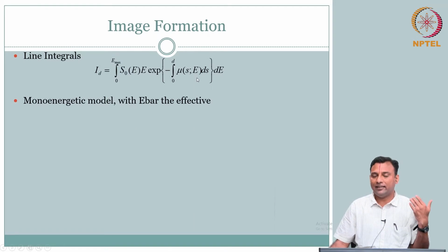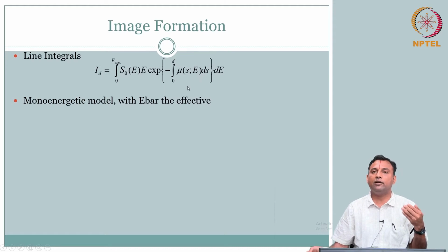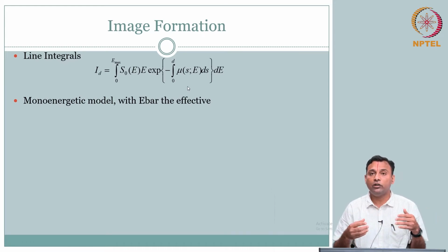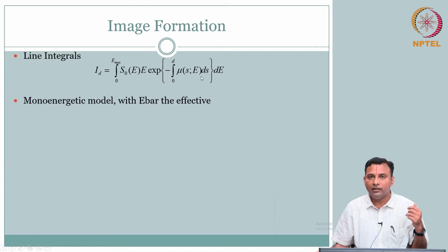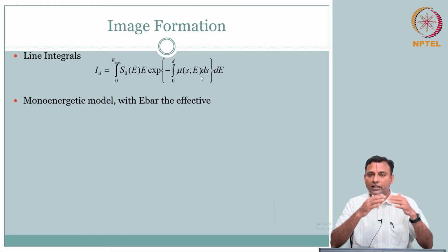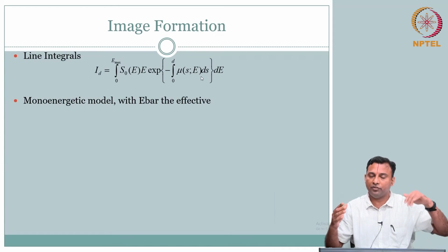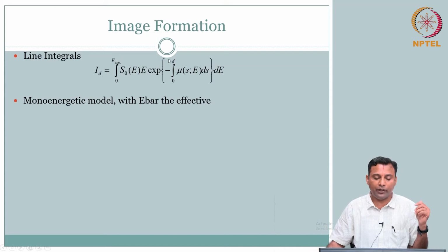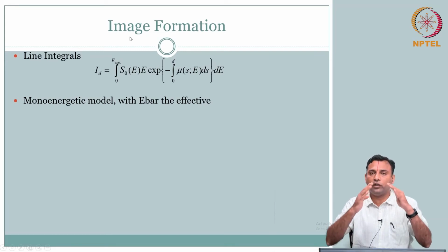But again, like I said, it is technically a function of E, but in the instrumentation we also covered where CT differs from projection radiography with respect to all the filtering and so on. We are deliberately making it harden. What did we mean by hardening the beam? You have a spectrum of energy, you are shaving off and reducing the bandwidth. The idea is that I am trying to get to monoenergetic. I want to reduce the energy distribution.